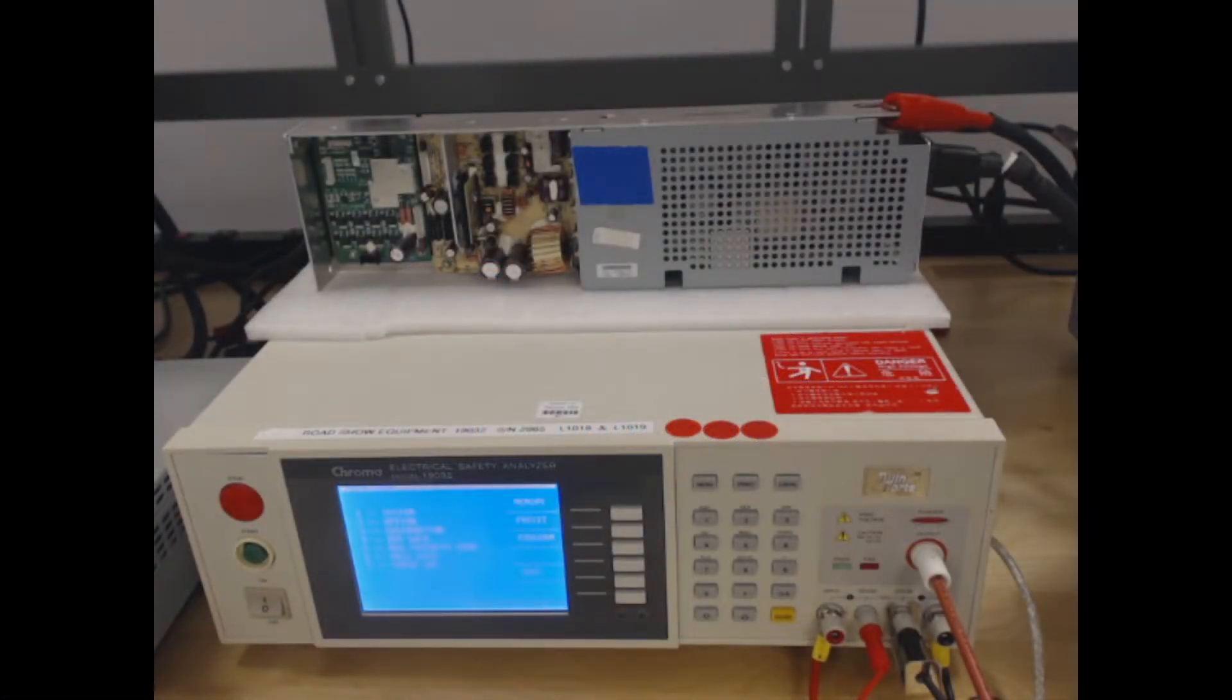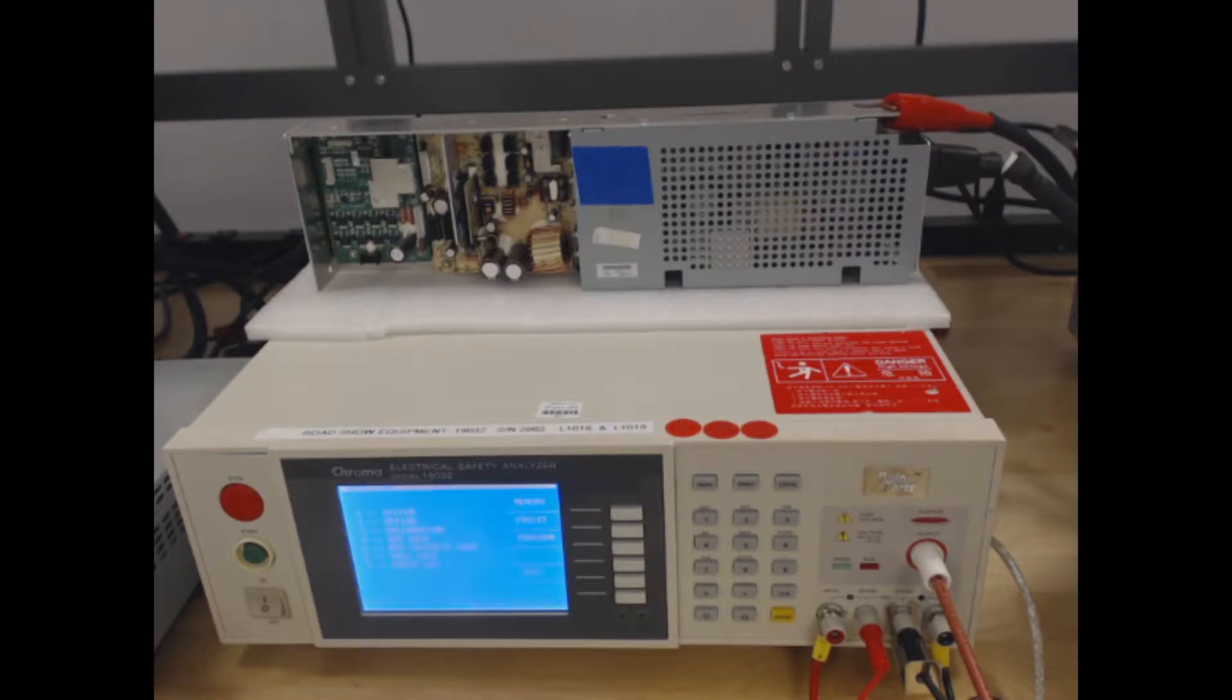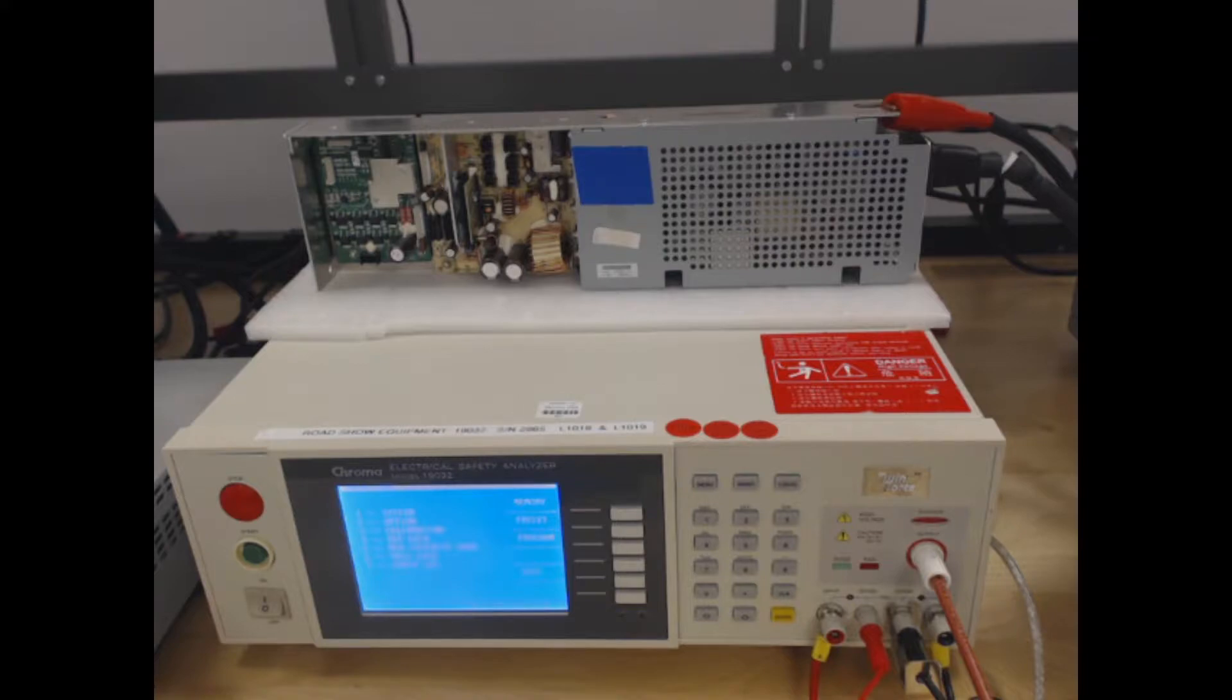Hey everyone, today I'm going to be showing you a ground bond test using the Chroma 19-032 Electrical Safety Analyzer. The purpose of doing a ground bond test, rather than the more traditional ground continuity test, is to ensure the integrity of your ground conductor.